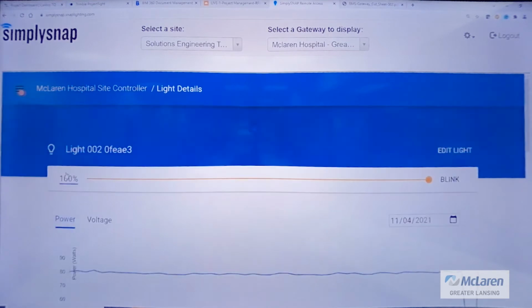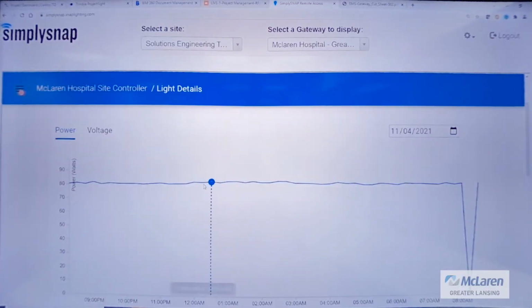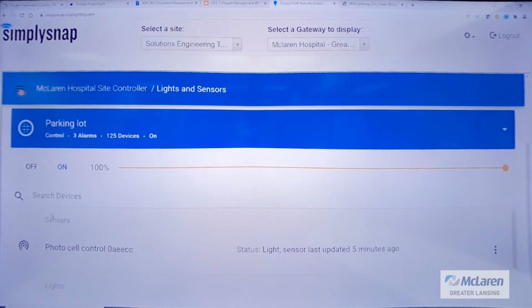In some cases, it depends on how they've got it wired to the drivers. I don't know if these fixtures have more than one or not, but you can go in and look at the power data on one of these. So for example, if you had one light, you could get into the system and check if our controller was communicating, and check to see if we're actually seeing any power data from it or not. I've used that before to determine that just an LED driver, one of multiple drivers within that fixture, had failed for some reason. You could get an idea that we weren't seeing any power coming from the driver, even though our controller was still operating. In other words, as long as we still have communication to our controller, and as long as power is making it to it, we can get some information about the LED drivers and whether or not they're pulling power from the system.